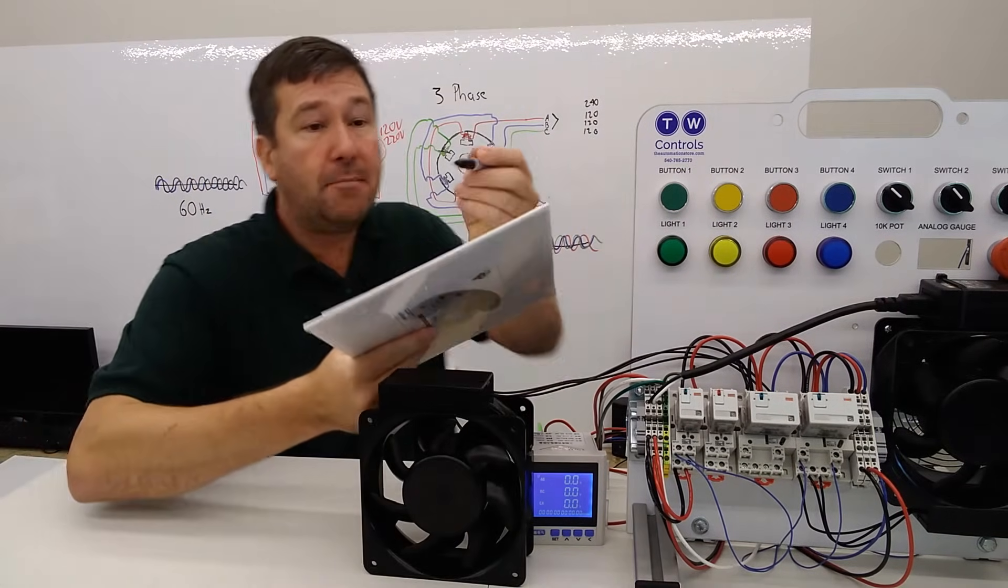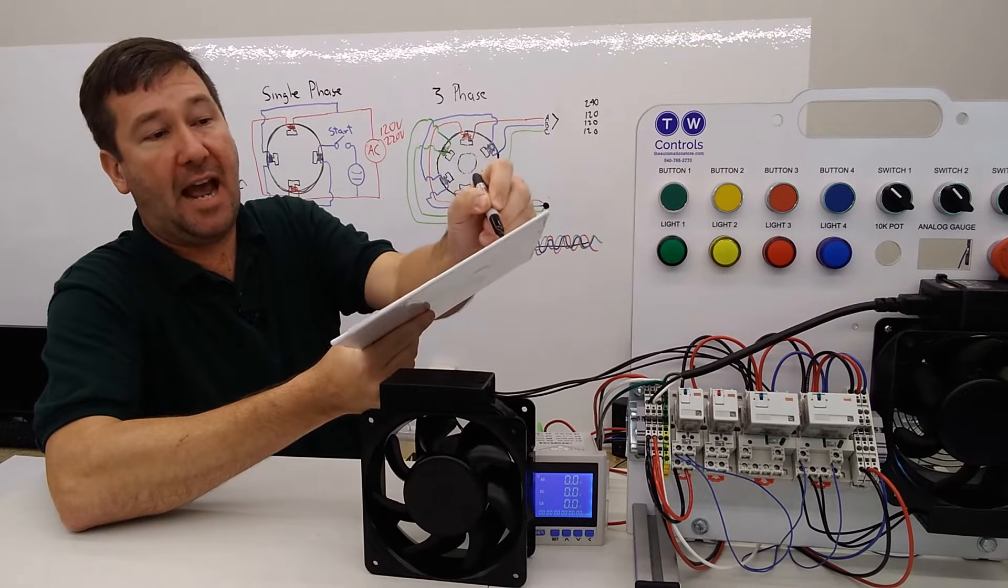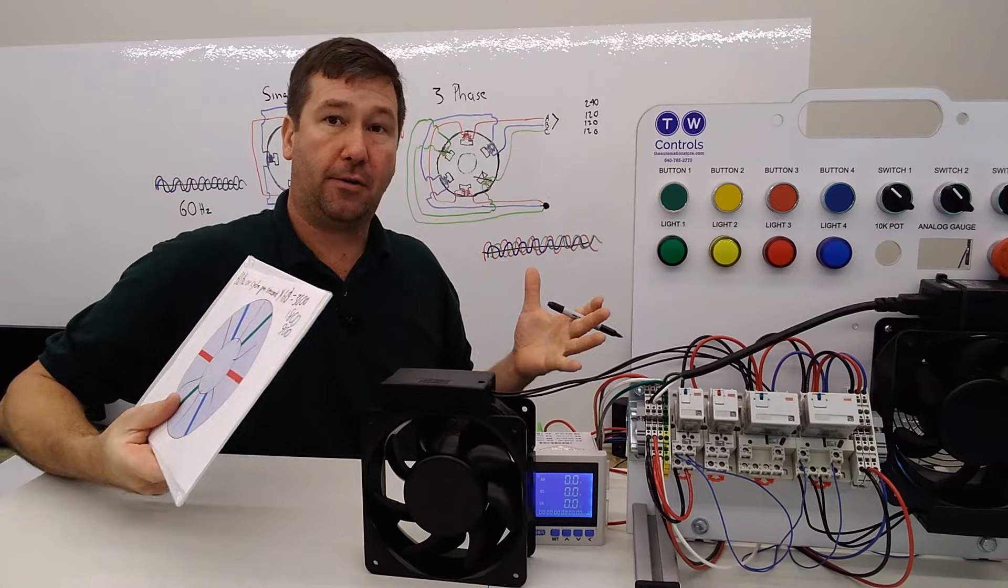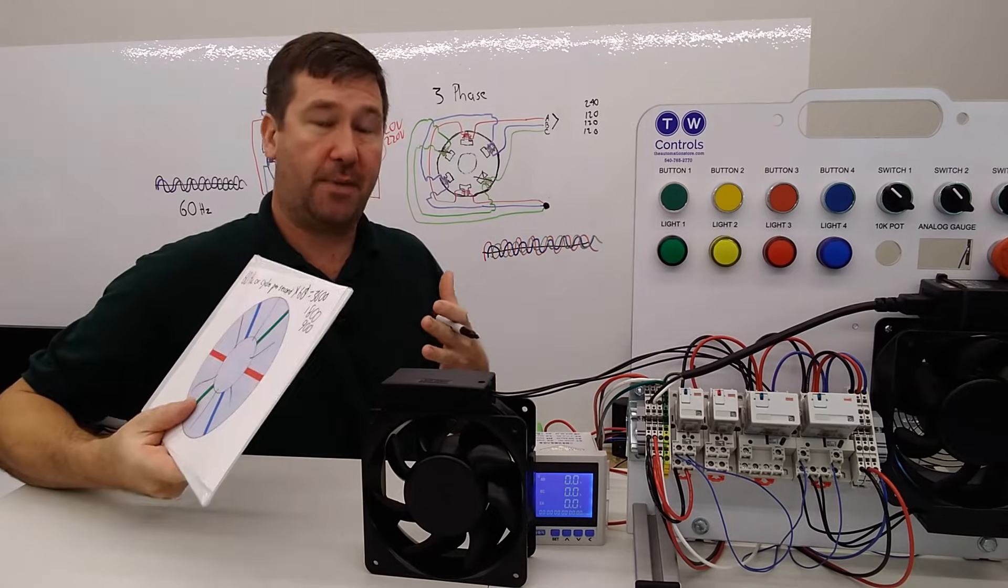And if you had, say, an eight-pole motor, it would be 900 RPM. Every time you go double your poles, you're going to split your RPM in half.